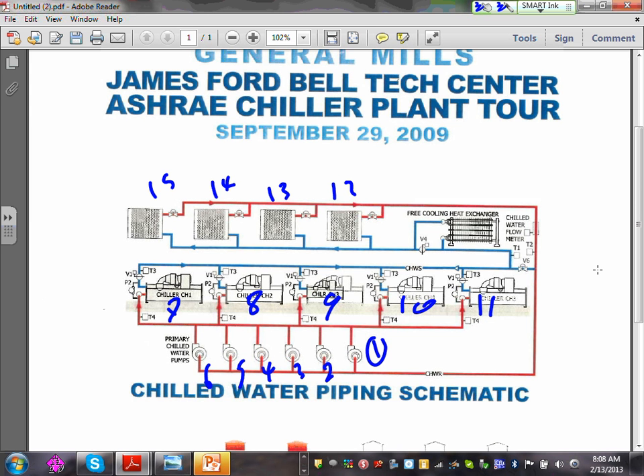Does it make sense, guys, how the system gets bigger? They parallel. Remember, Jeff, how we paralleled generators when we run out of juice? Exactly. When they run out of chilled water or hot water, what do they do? They run them in parallel. You can see the red represents the hot water coming back. The blue always represents the cold water going into the air handling unit.